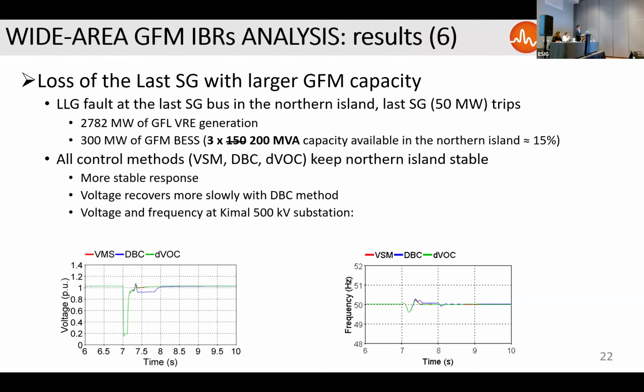So to mitigate this problem, the thing that they tested is to increase the capacity of the converters, and instead of 150, they were using 200 MVA rated converters. The initial power flow was still the same, 100 megawatt at each of the converters, but just because we have more capacity during the transient, the converters can contribute more to the stability of the grid, and we stabilize much faster than before.